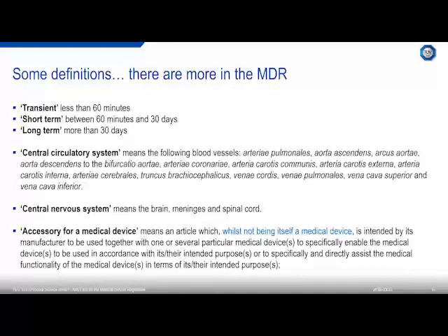For example, the use time of a device, whether it's transient, short-term, or long-term, is very important. Also the definition of the central circulatory system, the central nervous system, and an accessory of a medical device. A lot of manufacturers talk about accessories when they talk about actual medical devices. An accessory is not itself a medical device. That's very important, and you need to take it into consideration. When you classify an accessory, it is classified in its own right. So there is a lot of information in this annex that needs to be carefully evaluated and used for your decision on classifying your device.